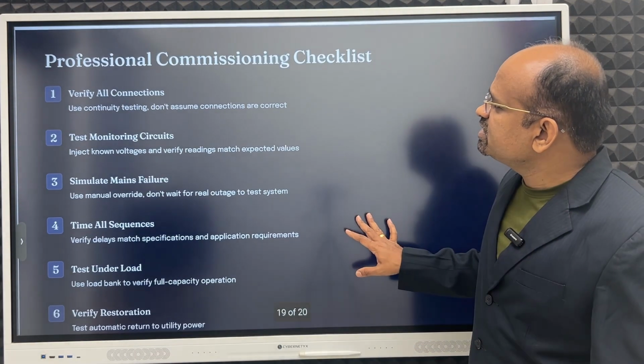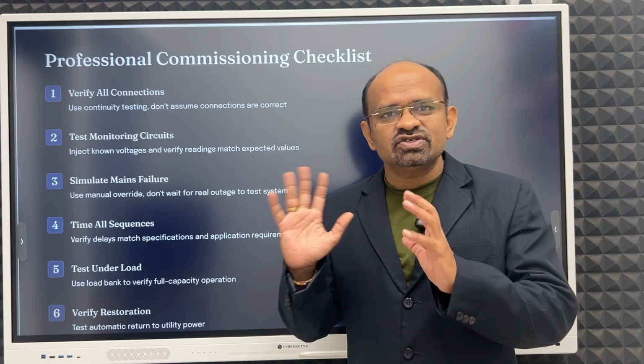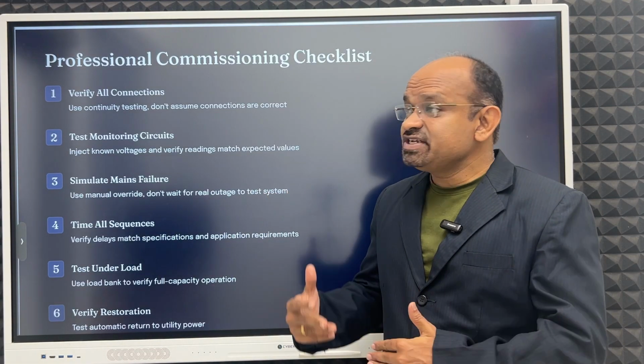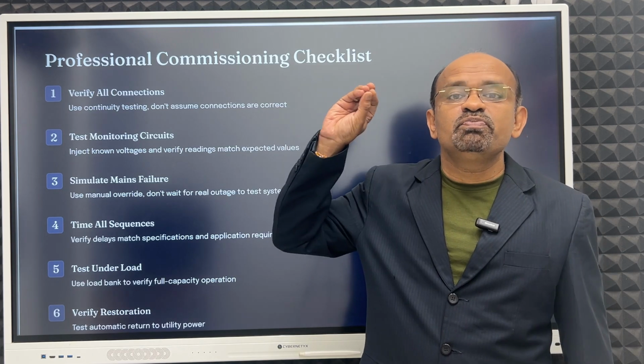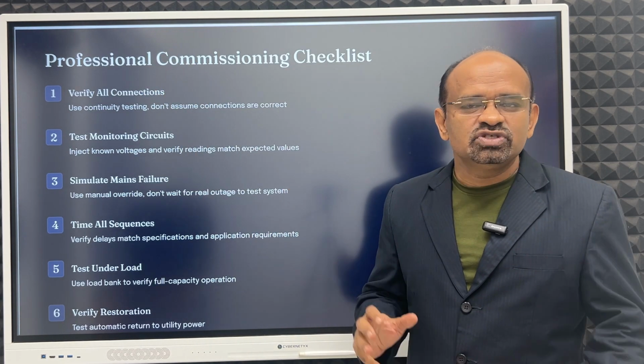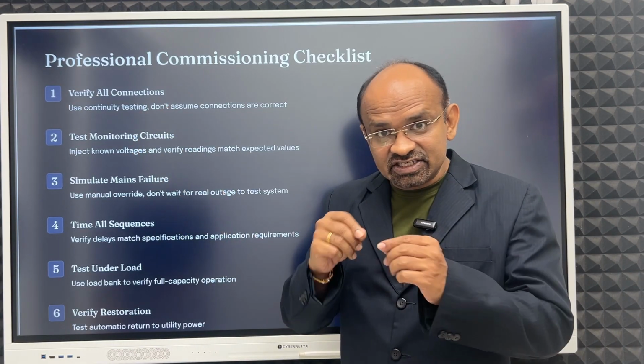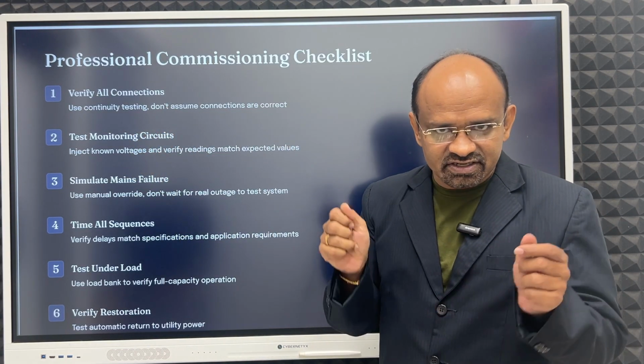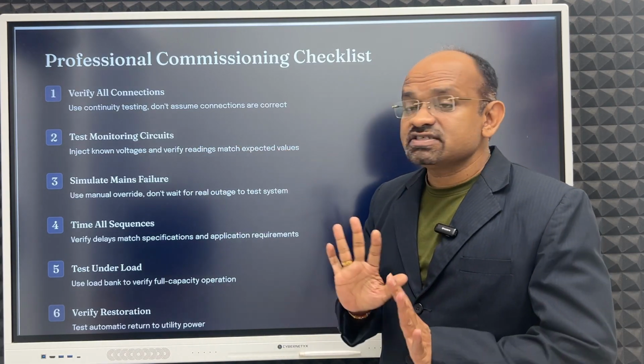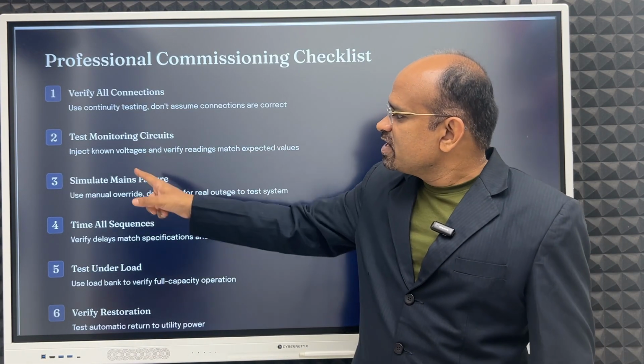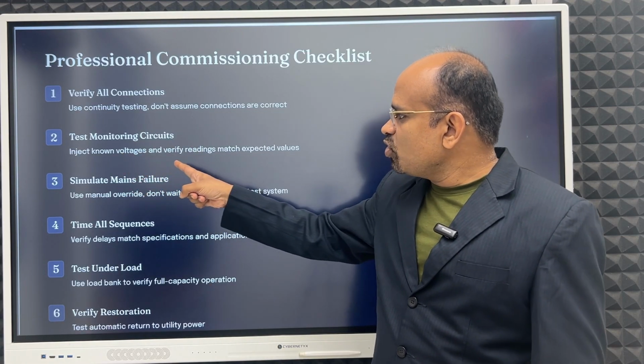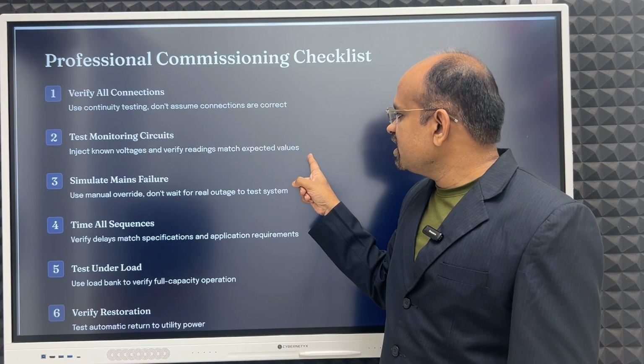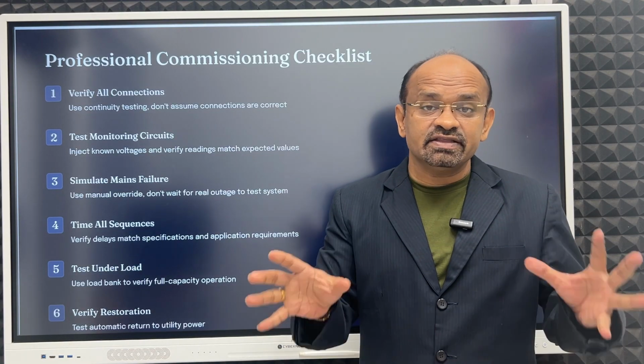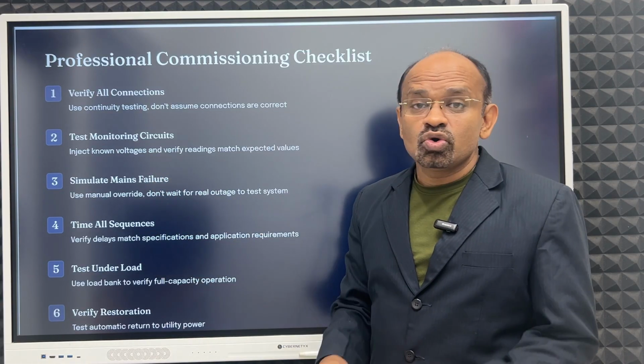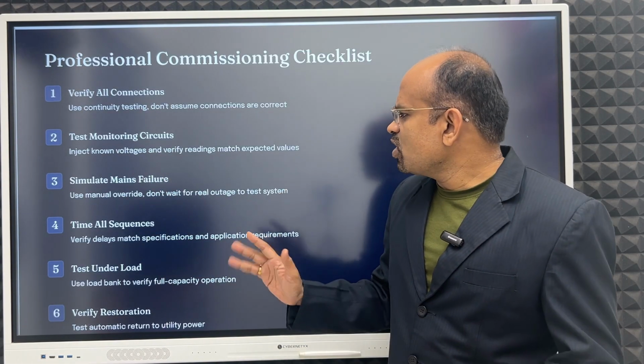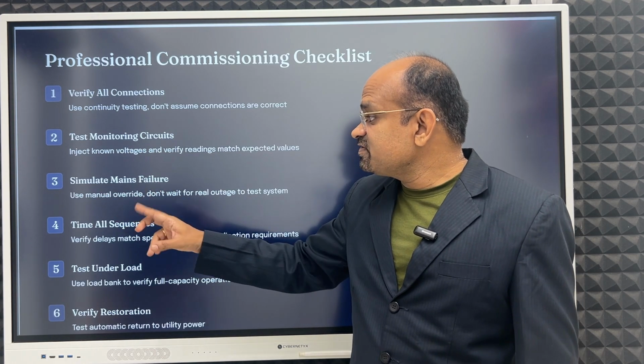Now, professional commissioning checklist. Now you have installed the AMF panel. While commissioning, what to check before we put it in normal operation? We should check all the parameters and verify all the connections. Use a continuity tester; don't assume connections are correct, you should check. Then test monitoring circuits: inject known voltages and verify readings match expected values. Monitoring circuits are there, so you should inject known voltages and check that they match normal operation. Then simulate mains failure.